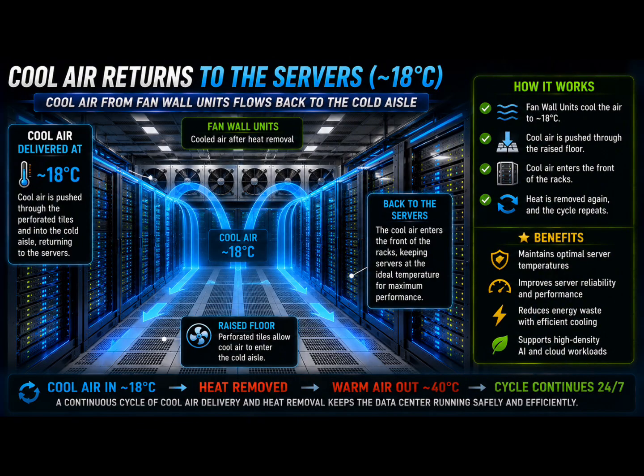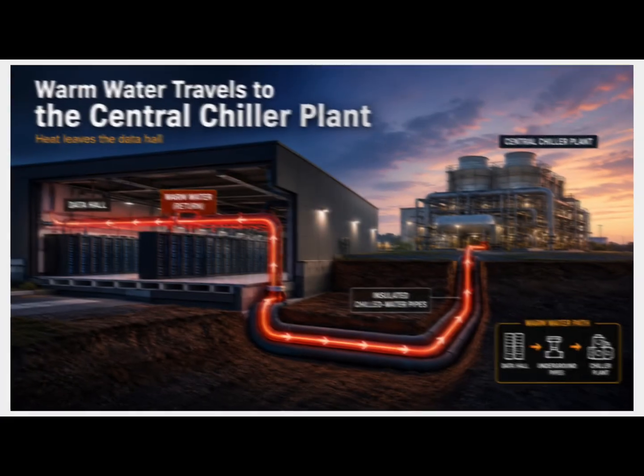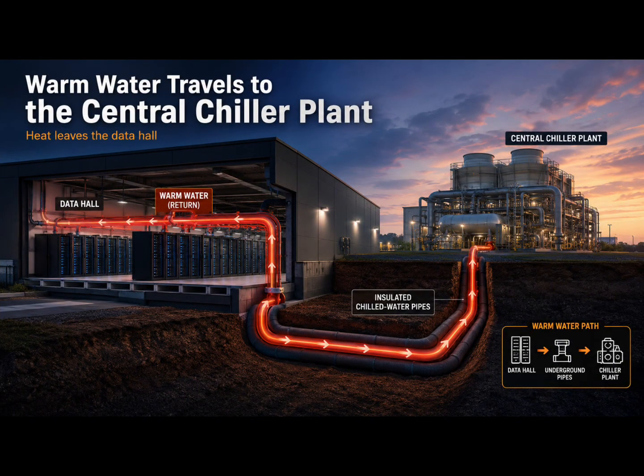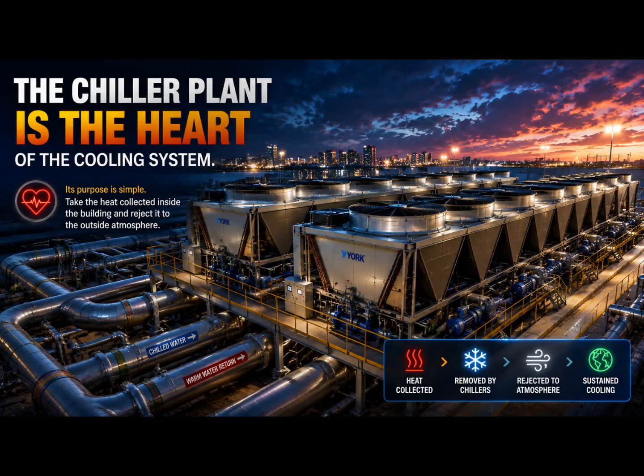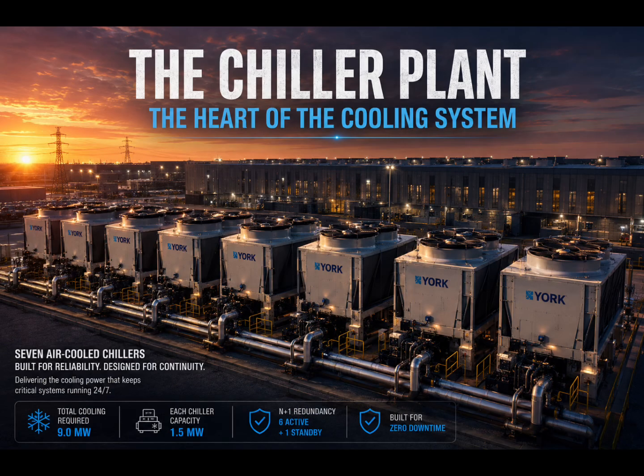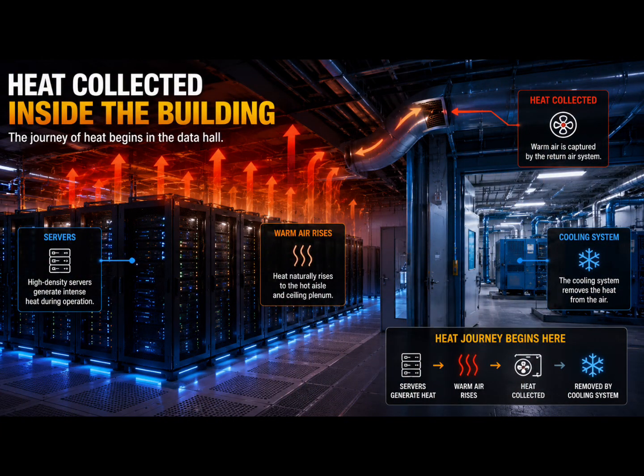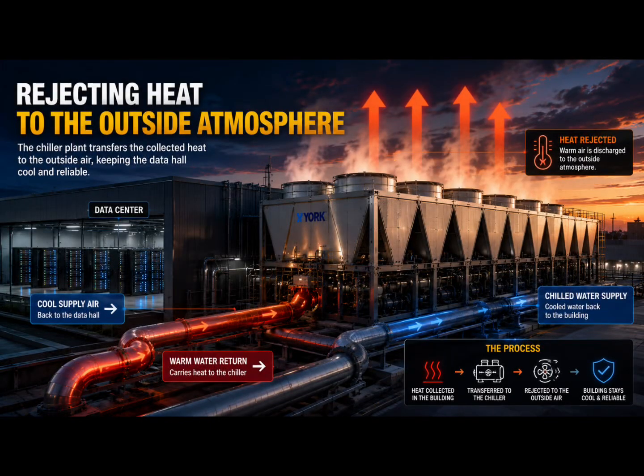The servers draw it back in, and the entire cycle begins again, second after second after second, 24 hours a day, 365 days a year, without stopping. But the journey isn't over yet. The chilled water has now become warm. It carries all the heat removed from the servers. That warm water leaves the data hall and travels to the central chiller plant. The chiller plant is the heart of the cooling system. Its purpose is simple. Take the heat collected inside the building and reject it to the outside atmosphere.